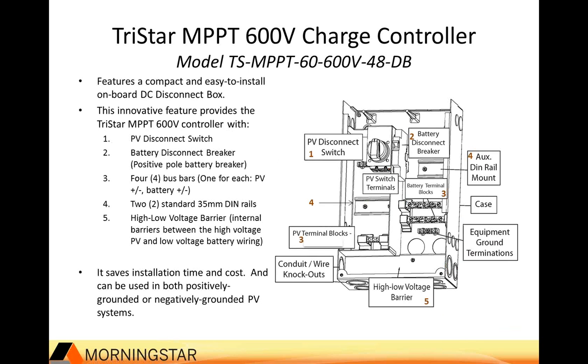Okay, moving right along. This is an internal shot of the disconnect box, so you can get an idea of what you're seeing inside. Let me try my laser pointer out here. You can see here's the disconnect for the PV. We have DIN rails located here and here. Here is all of your battery terminal wiring blocks and your PV terminal blocks on the other side. This is a voltage divider that's going to keep the high voltage component separate from the low, and then we have a pass-through that allows you to run both high and low voltage wiring separately through the bottom. And if you made up 4 of these devices, then you can run them all through the bottom of the controller. So this is Morningstar's first exploration into some of these additional balance of system components that we're beginning to offer with the products to make them easier to install.